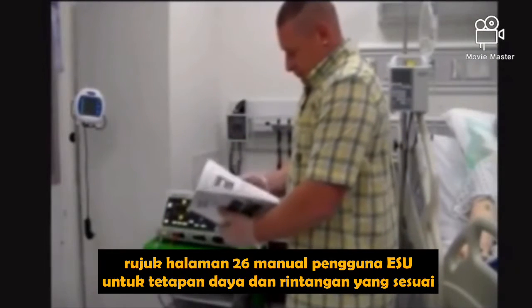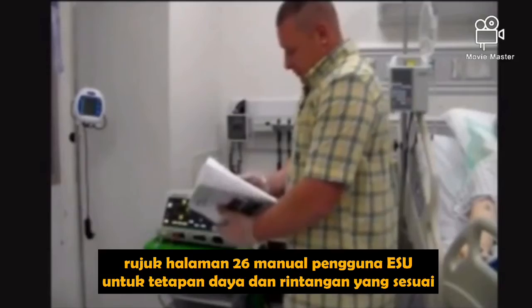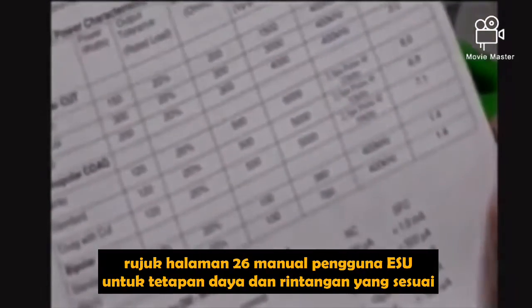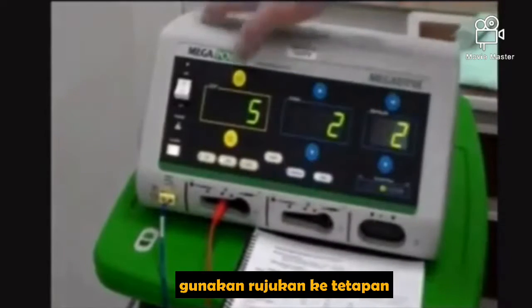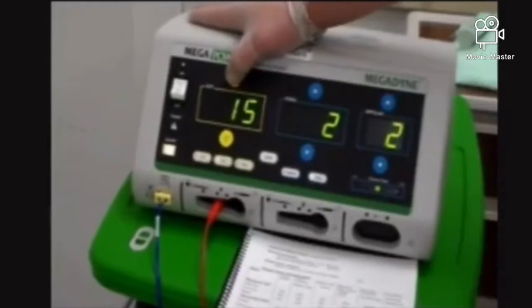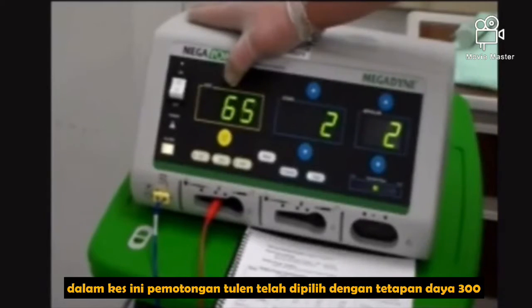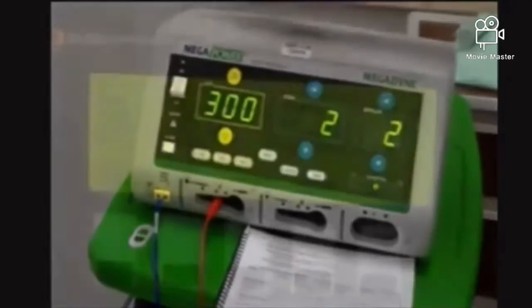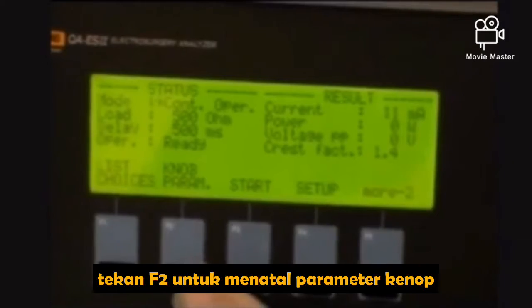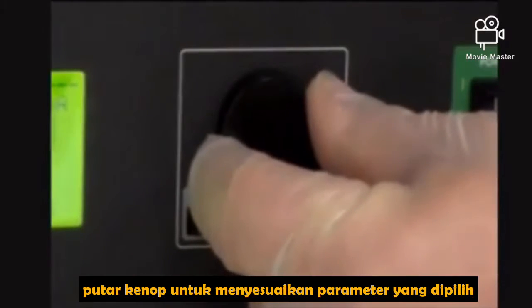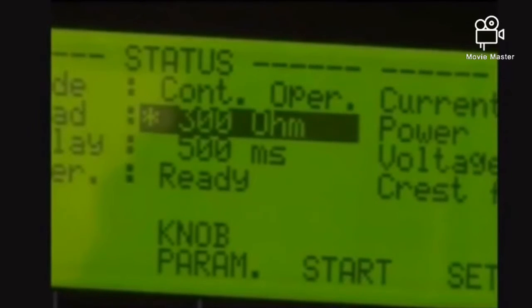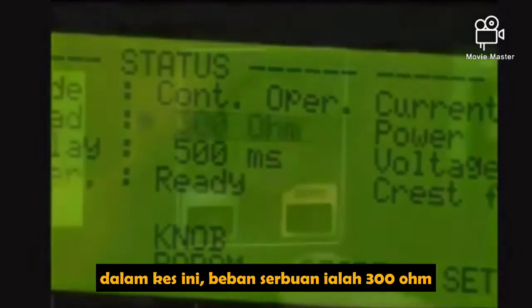Refer to page 26 of the ESU User's Manual for the appropriate power and resistance settings. Apply the referenced settings. In this case, Pure Cut has been selected with a power setting of 300. Press F2 to scroll through the knob parameters. Rotate the knob to adjust the selected parameter. In this case, the rated load is 300 ohms. Press the Enter key to finalize your selection.